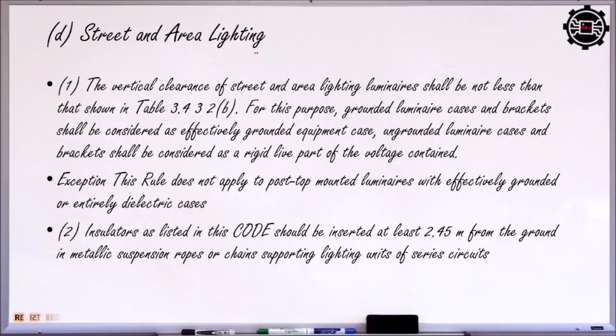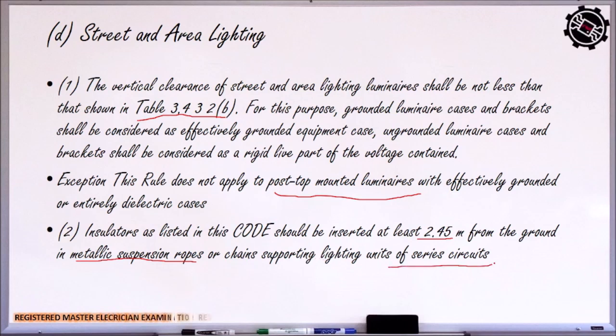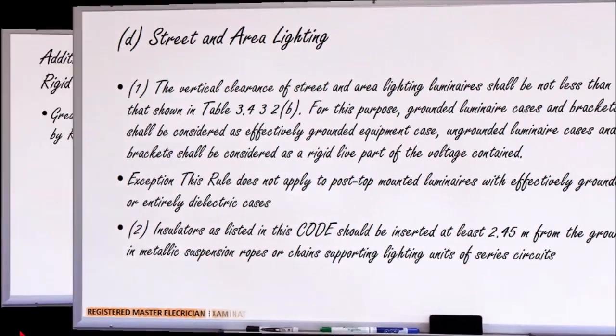The street and area lighting. So the vertical clearance for street and area lighting luminaires shall be not less than shown in table 3.4.32b. So for this purpose, the grounded luminaire cases and brackets shall be considered as effectively ground. So the rule does not apply to post-top mounted luminaires. So yung mga luminaires na sa taas which are grounded, no? Insulators as listed in this code should be inserted at least 2.45 meters from the ground in metallic suspension ropes or chain supporting lighting units of series circuit. So meron tayong nakalagay na insulation every 2.45 meters for our area and street lighting.